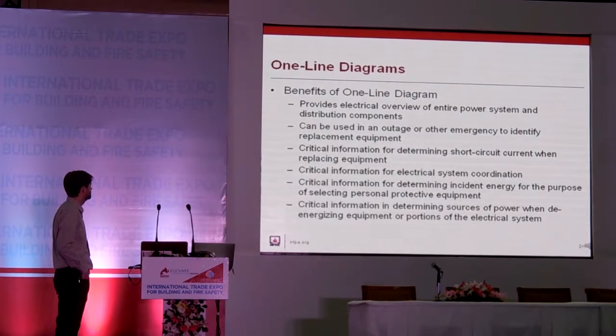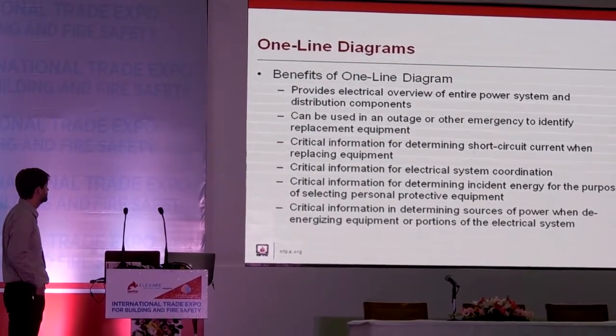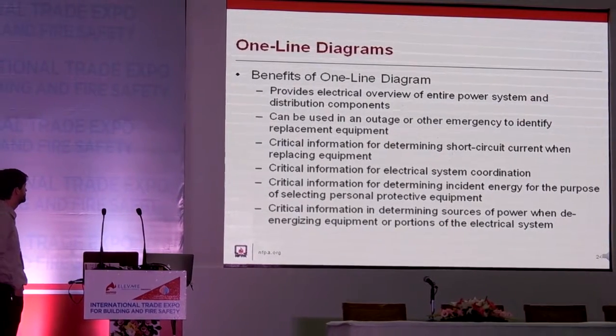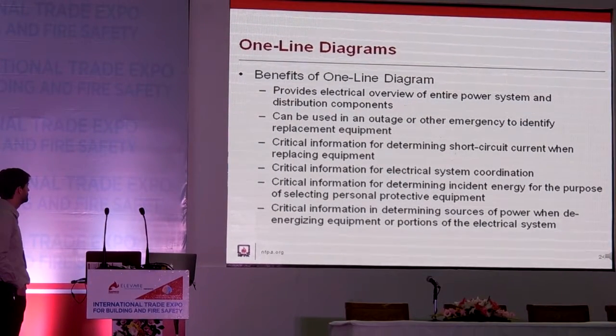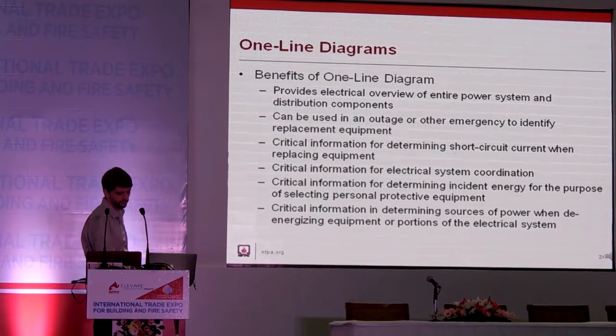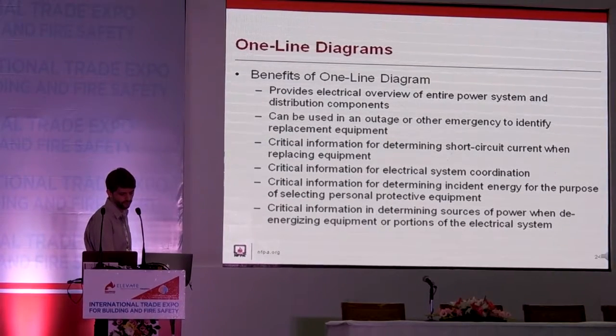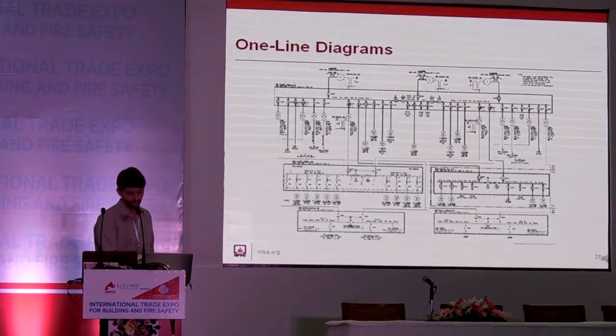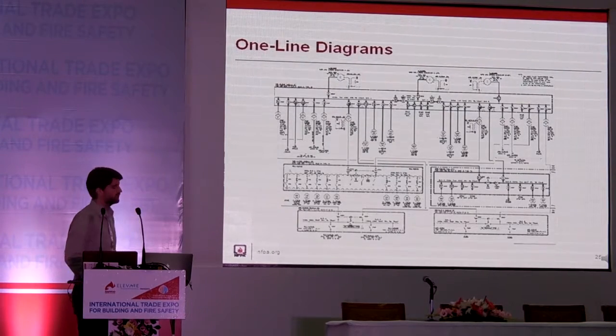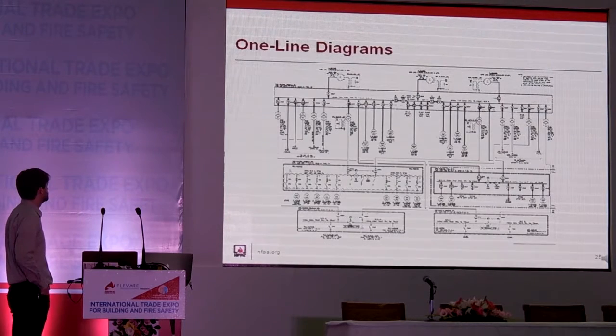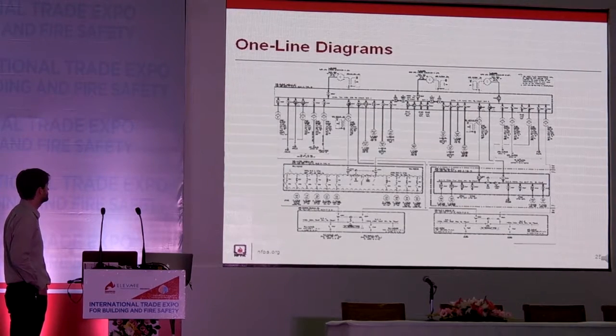Finally, one-line diagrams are very important when it comes to shutting power off to equipment and determining where all the sources of power to a piece of equipment are located and where they can be disconnected. In some cases, equipment may have multiple sources of power. The one-line diagram is a very important piece to identifying those sources. Here's an example of a one-line diagram with a relatively comprehensive amount of information. Again, the more information in a current one-line diagram, the easier it is for maintenance personnel and for safety personnel to make sure the jobs are being done correctly and safely.